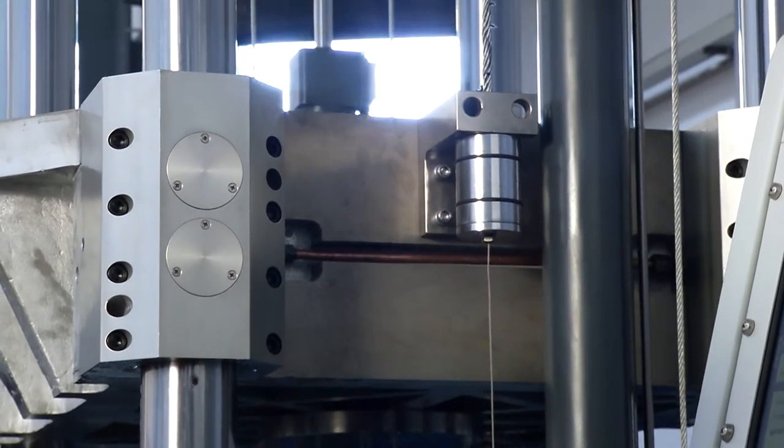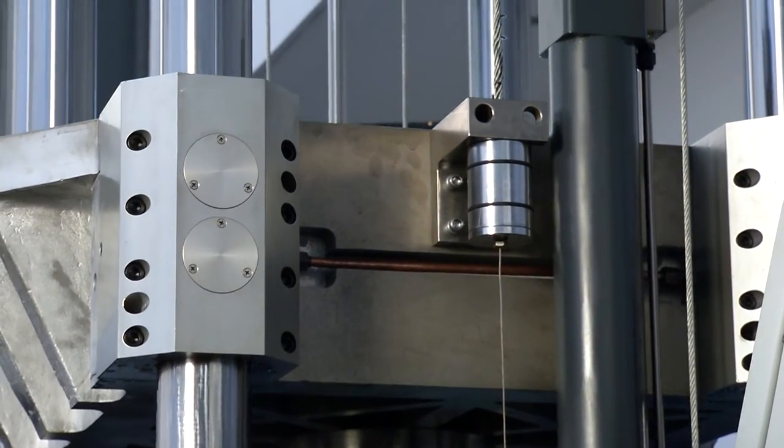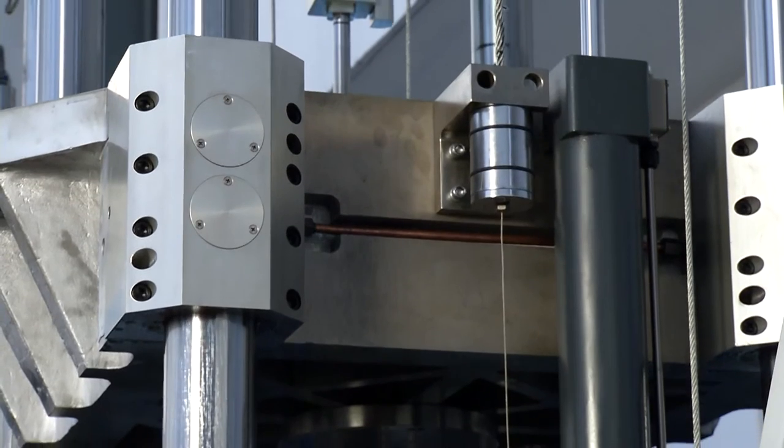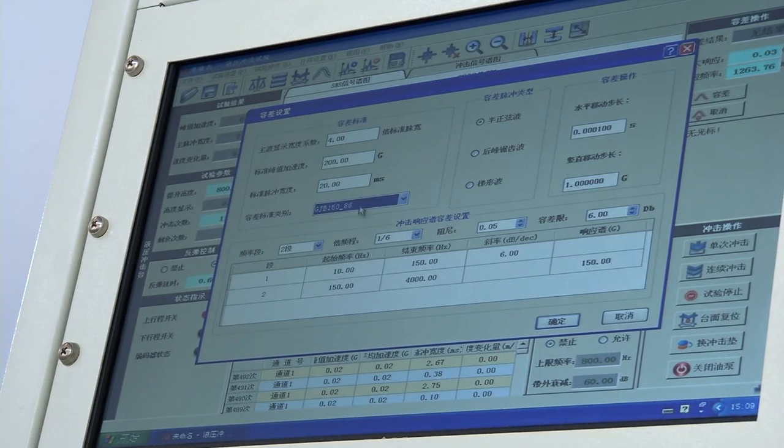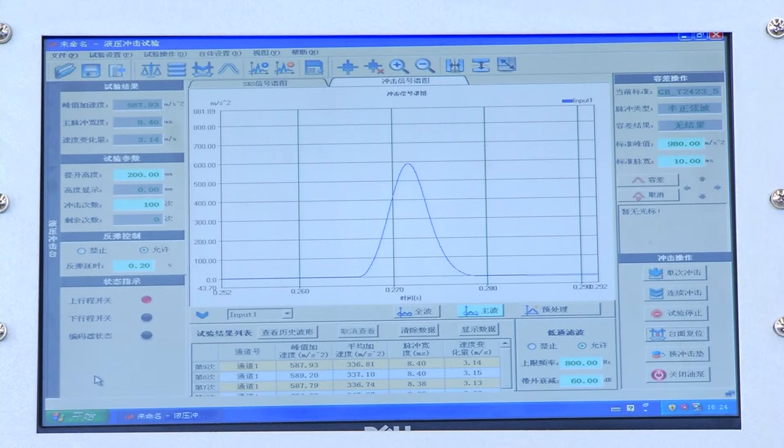This test stand is hydraulic driven and performs free-fall shock tests. It can replicate regular half-sine waveform, post-peak sawtooth waveform, and square waveform, which meets standards of IEC, MIL, GB2423, and GJB150.